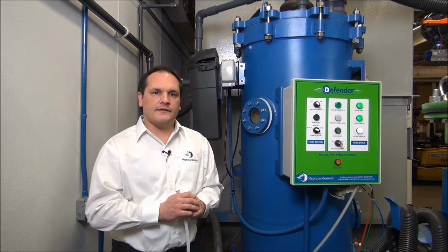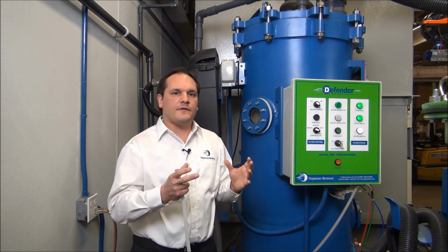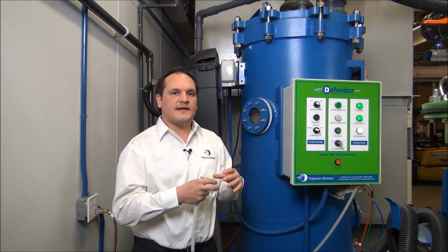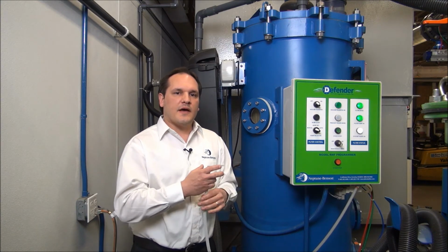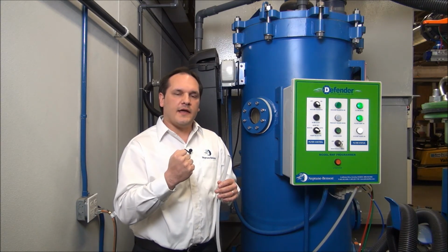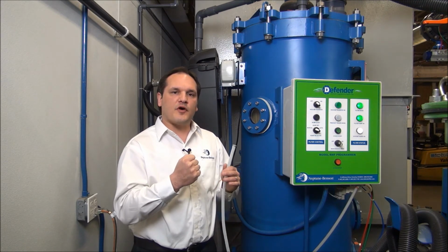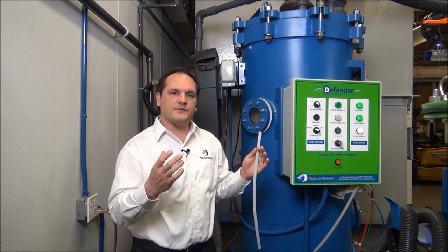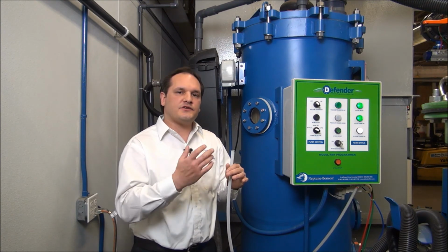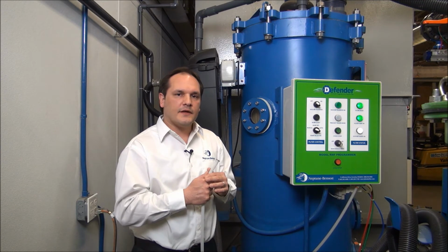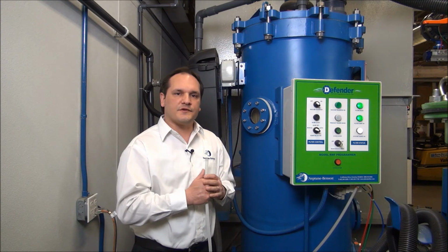Every day we want to conduct a bump process. Bumping is the ability of the filter to remove the perlite media from the flex tubes, send it into solution, and then go into a pre-coat process again. Remember, if my fist was a particle of perlite media, 85% of it is open void space just waiting to collect dirt and debris. It's through this bump process of releasing that media from these flex tubes and then going into a pre-coat process again and rearranging that media, essentially turning the pancake over to cook the other side. Again, this bump process will take place on a daily basis, and this is what will extend the filter cycle.